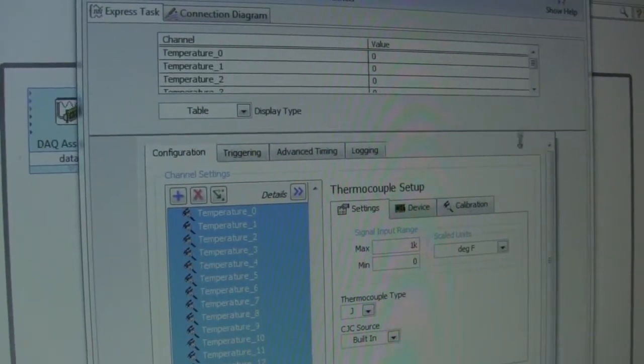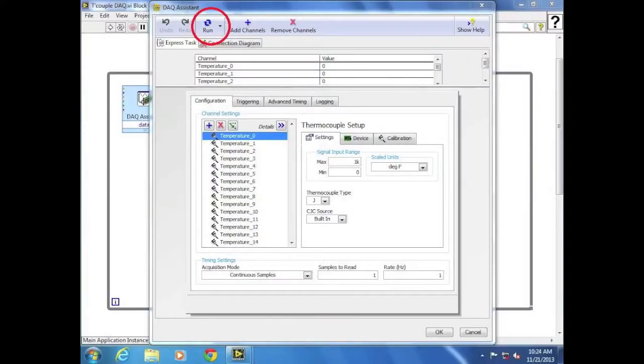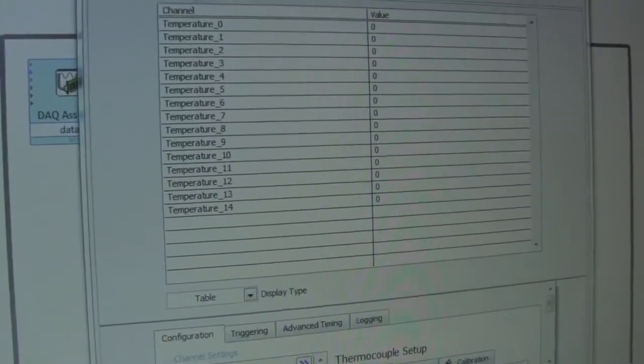Pull down the drop-down screen so that all channels can be read, and select Run to test each channel. Each channel number has a corresponding thermocouple.